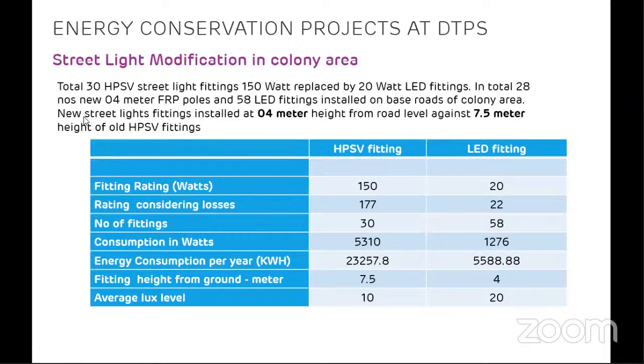So in the colony area also we had 30 HPSV street light fittings, 150 watt each. They were replaced by 20 watt LED fittings. A total of 28 four-meter FRP poles and 58 LED fittings were installed. They were initially at 7.5 meter height for the HPSV fittings, so we reduced the height of the pole to 4 meter. This was done to ensure that the lumens, or the light available at ground level, was unaffected. So we had to reduce the pole height from 7.5 to 4 meter while replacing the 150 watt HPSV with 20 watt LED fittings.